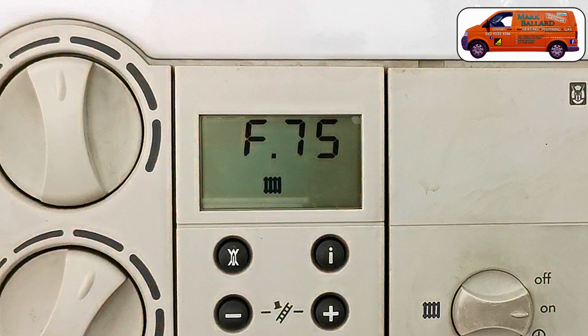Hello! In this video I'm going to show you how I go about replacing a pressure sensor in a Vaillant boiler, because the boiler is coming up with that F75 fault. Now, not all the pressure sensors are in the same position on the Vaillant boilers, but the process to replace them is exactly the same.